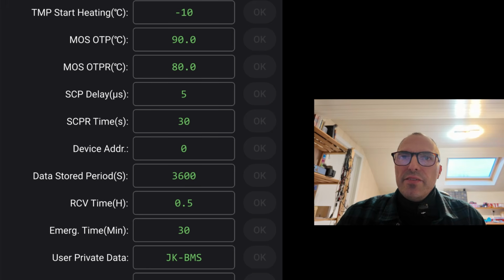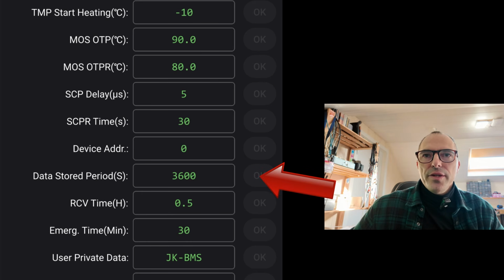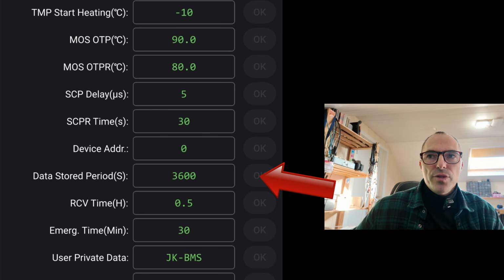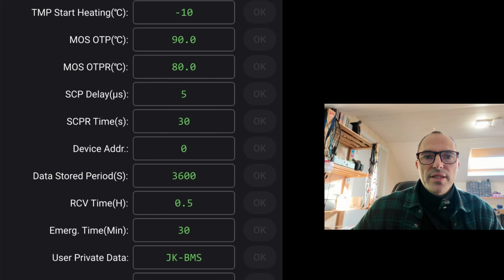Device address is the address you set via the dip switches on the front panel. The OK button is grayed out; you can only set it via that same front panel. With a first and only battery, I should set the value to 0. This is important if we want to access the battery via RS-485 and a computer. I will demonstrate this in a few minutes. Data stored period, 3600 seconds. Every hour it saves the values of the most important parameters. You can later access this data or import it into Home Assistant to generate nice graphs.